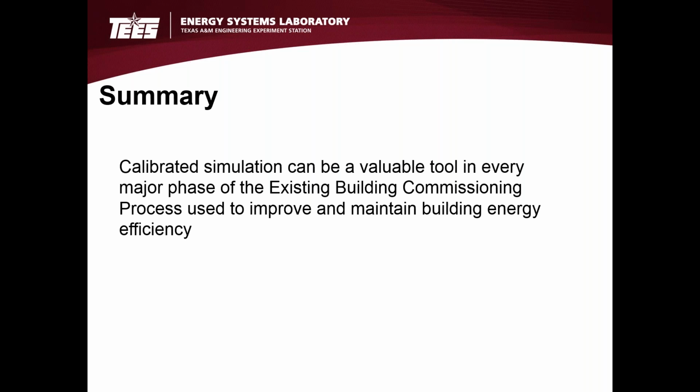Okay, that's a good question. In terms of construction details, we have purposely set our programs up so that they do not require detailed construction details. Because we find that very often the calibration process will conclude that the building is operating differently than the way the construction details told you it should operate.